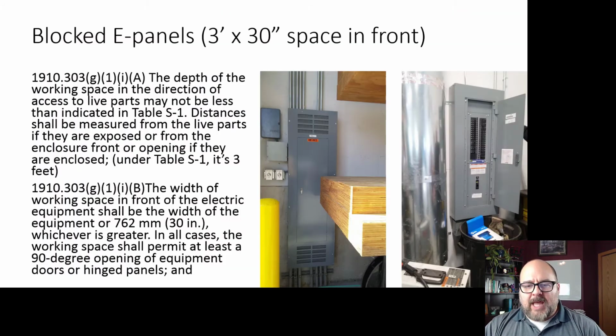Another issue is space to access a power center or circuit breaker panel. This circuit breaker panel is rated at 480 volts. You'll notice it doesn't have the arc flash sticker on it. This inspection was done over 5 years ago, I'm not sure how well versed I was in NFPA standards at that point, but they should have had that as well, though I'm not sure where you'd cite that in the OSHA standard. There is something on arc flash. If you can't open the door all the way, you can't properly access it or take the care you need. This wood is flammable, so if something happened, even a minor arc could catch stuff on fire and take down the whole building.